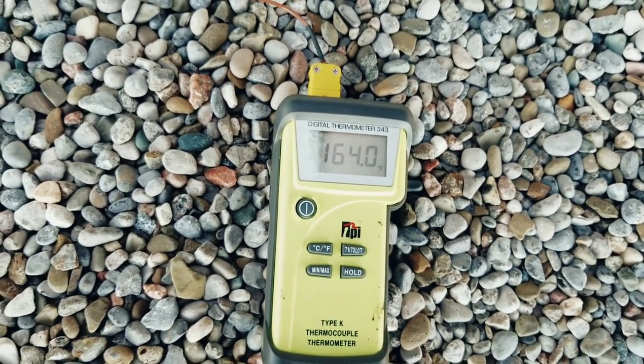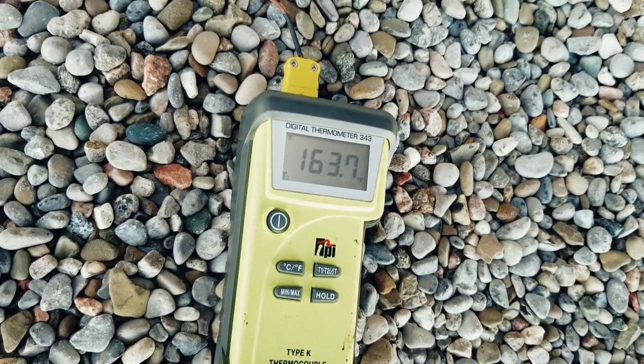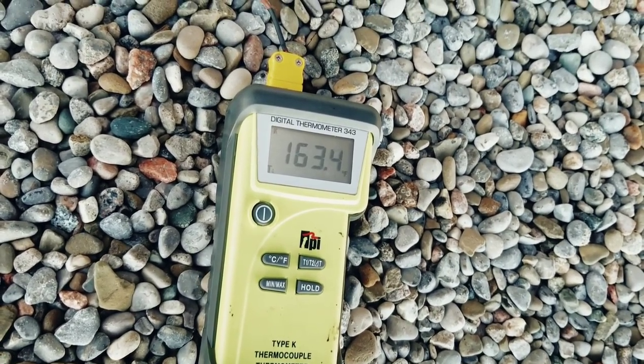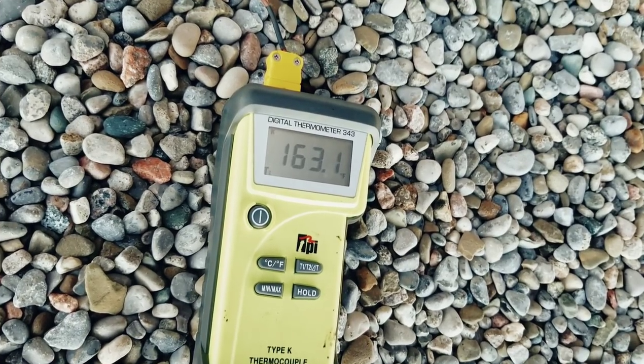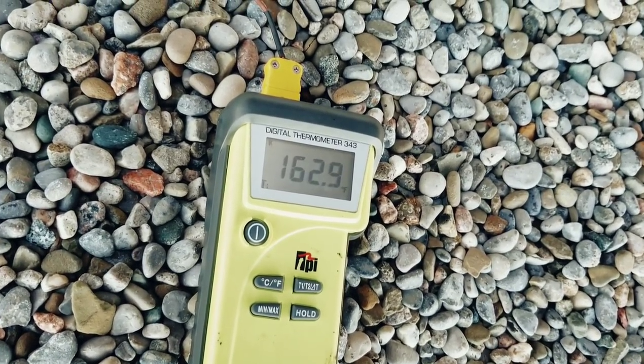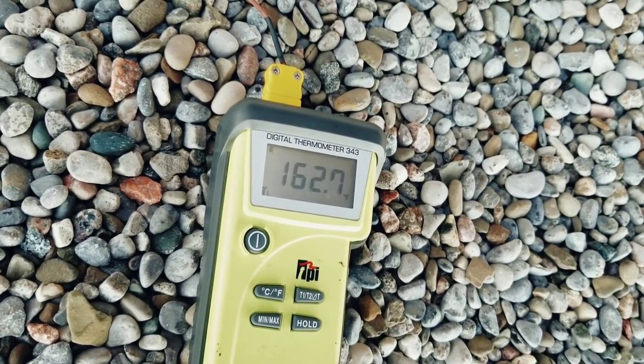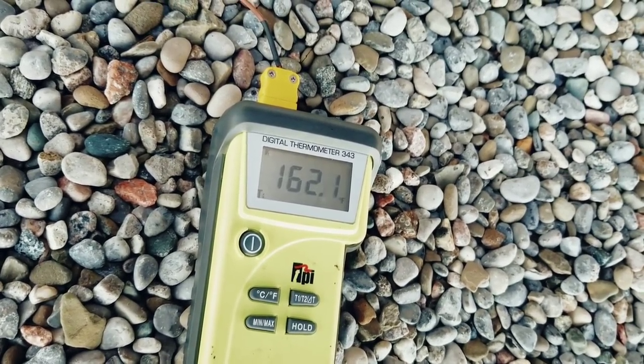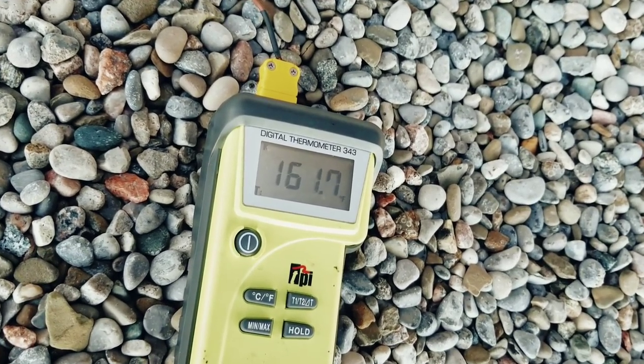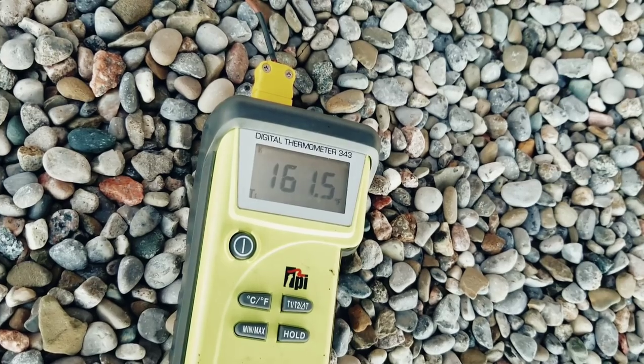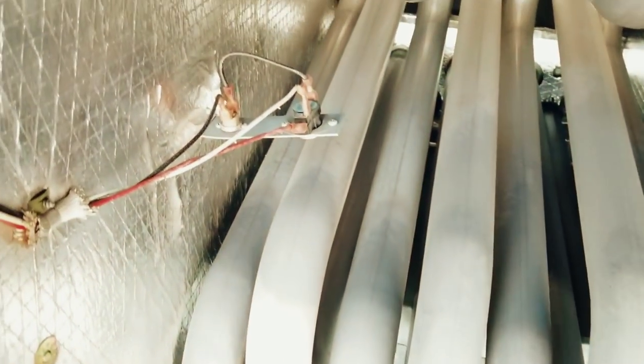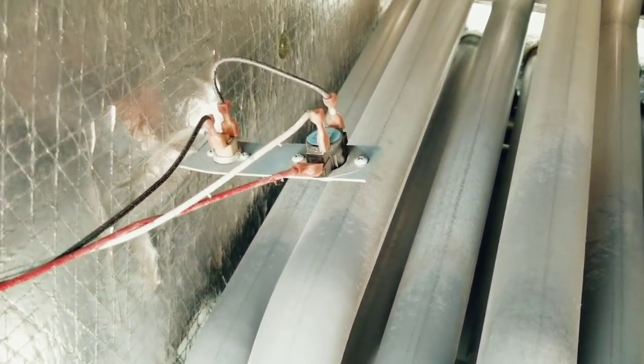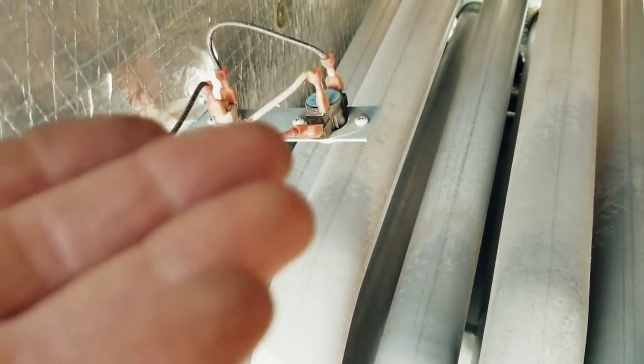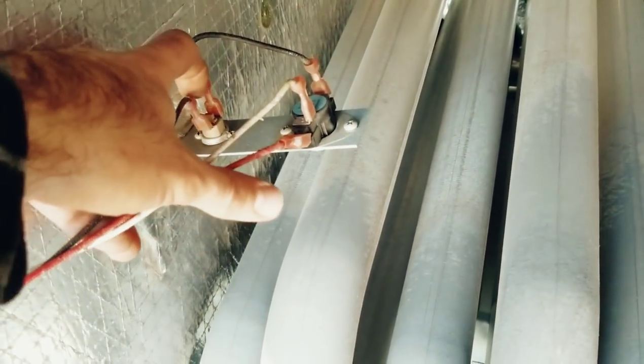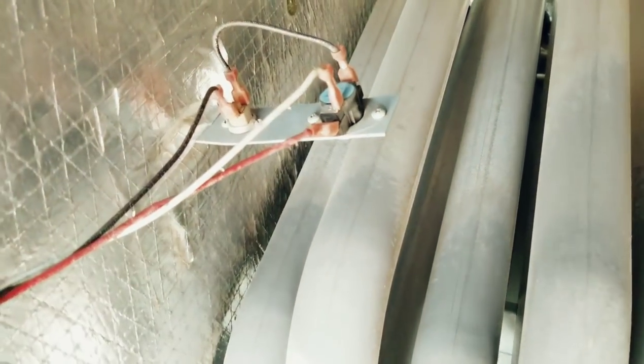So imagine on a really cold day outside, all 15 units in this warehouse running, the deck is going to get around probably 80 degrees because that warm air is not being pushed to the floor the way it should be. And then we kill the power to all of the fans and we kill all airflow in the warehouse. You could see how there's a potential there to trigger the high limit. So check this out, guys. After that machine was off for about 5 minutes with no airflow, the residual heat rising up off the heat exchanger actually tripped this manual reset high limit switch.